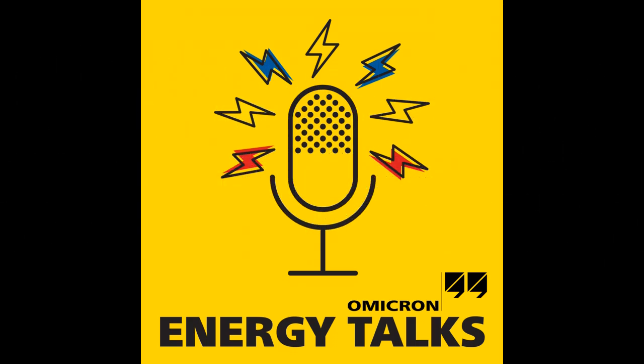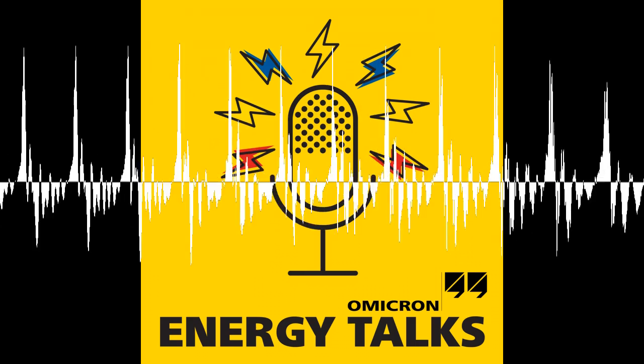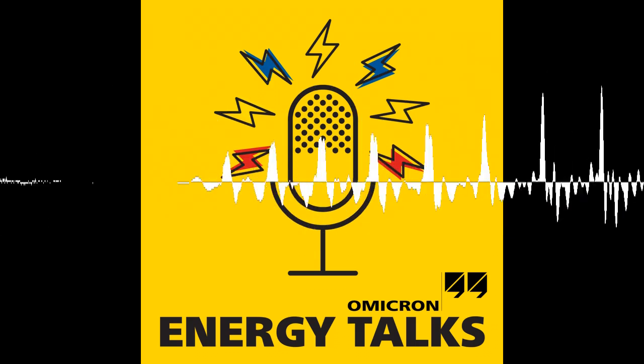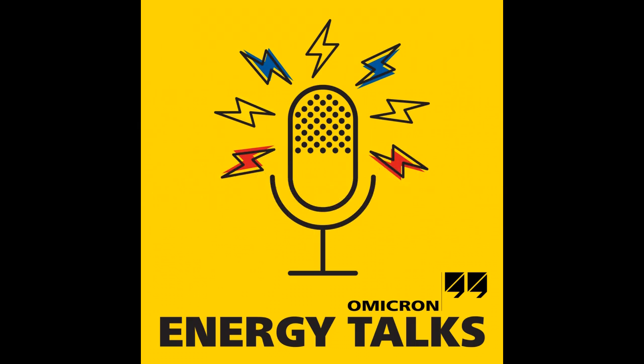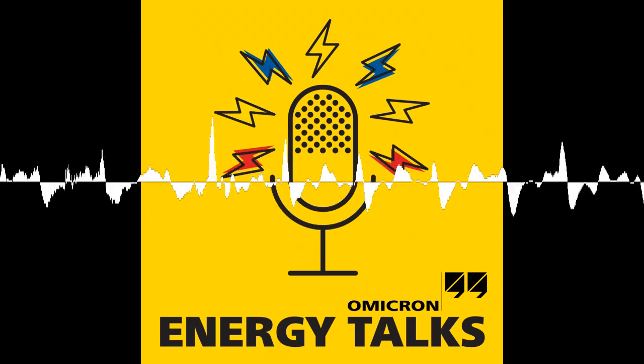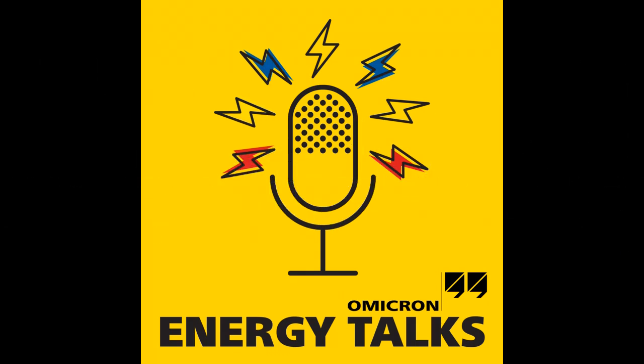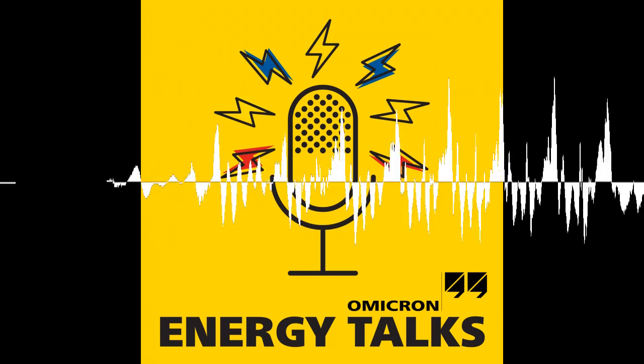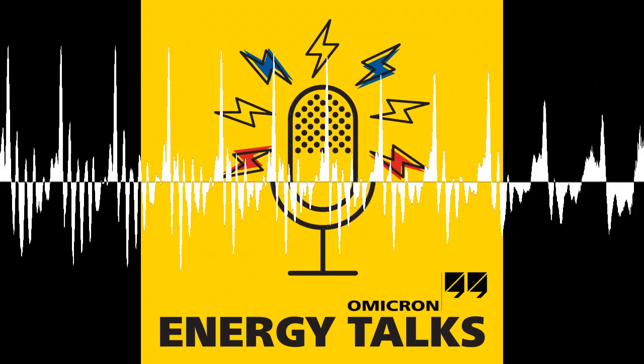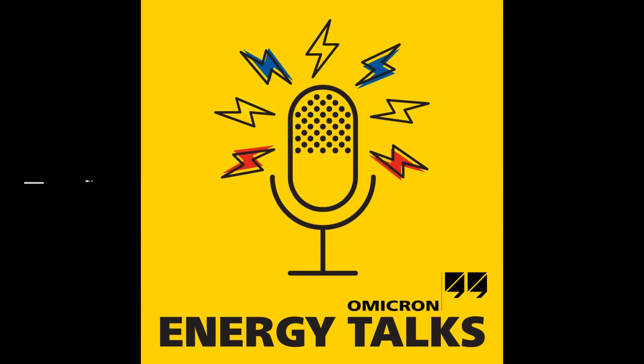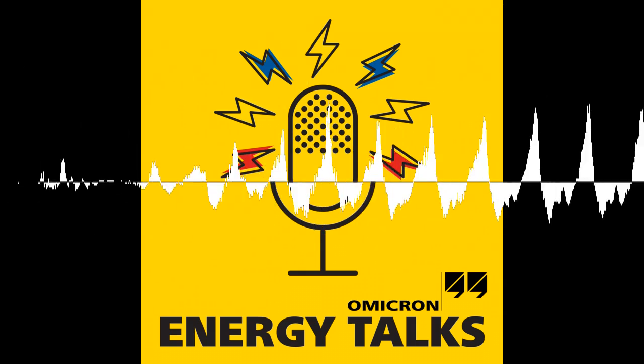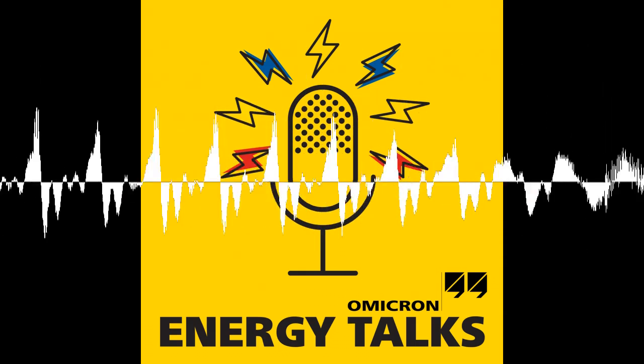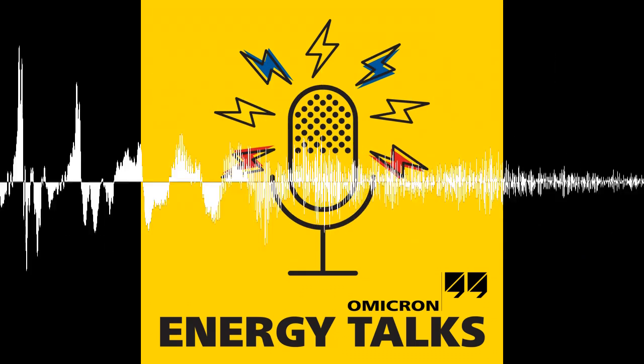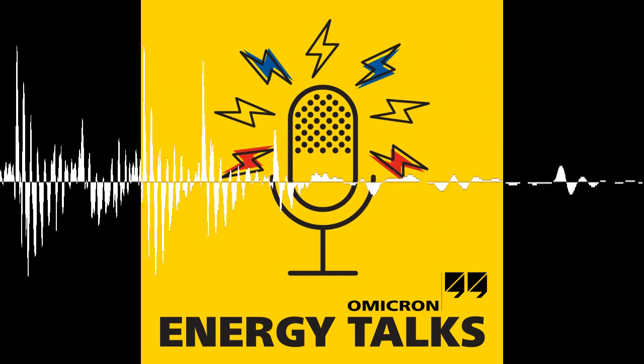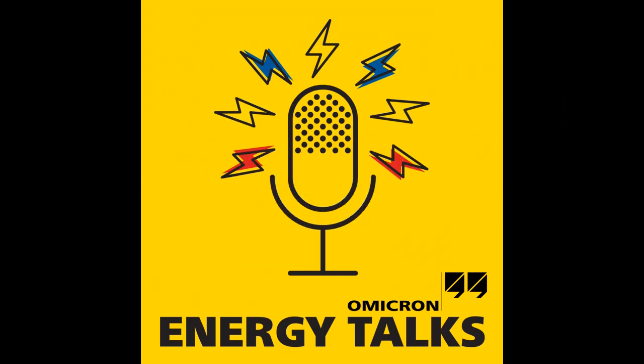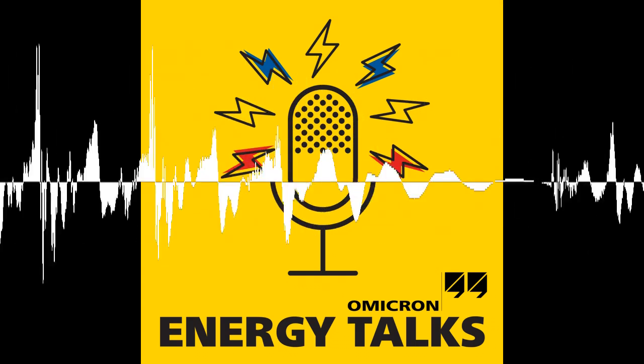The real challenge is noise, always. Noise means interference. It means we're looking for very small discharges, and these very small discharges, if you have a very noisy environment, can be hard to detect. And that's because the equipment itself is so sensitive that it's picking up not only the PD signal, but also the noise signals at the same time. Exactly. And a great deal of effort in creating the MPD went into technologies that discriminate noise versus PD and that help you evade that noise and make a perfectly valid measurement even in very difficult conditions.